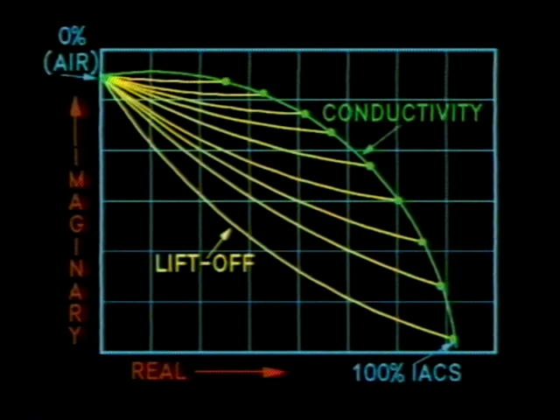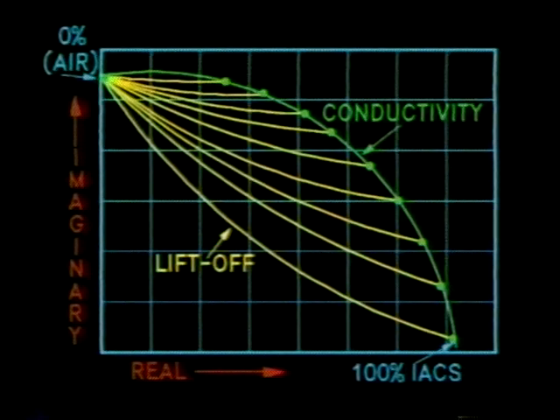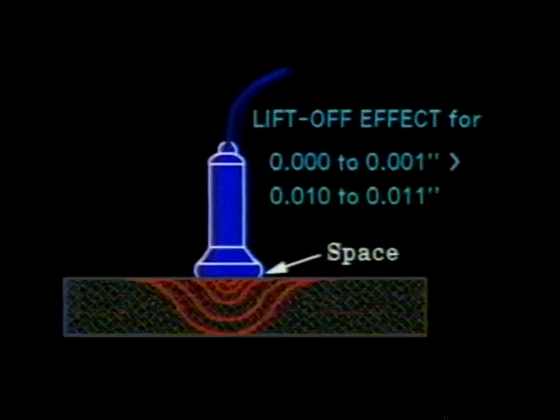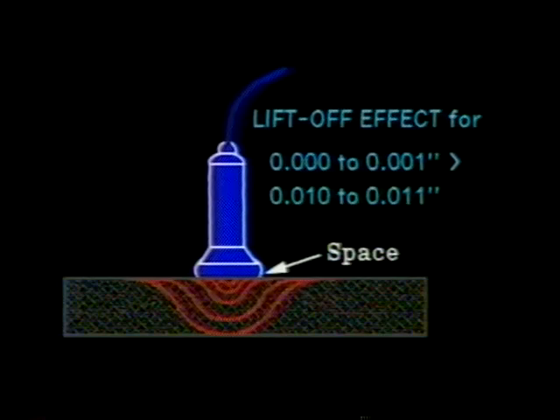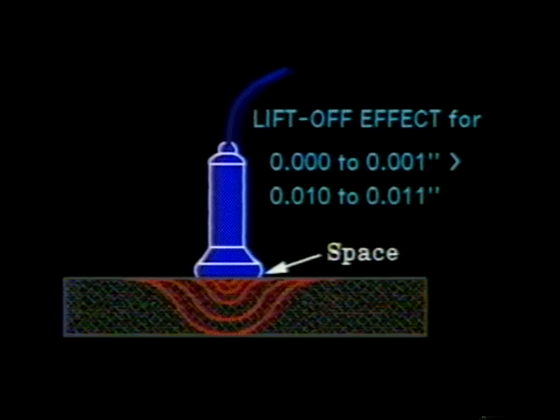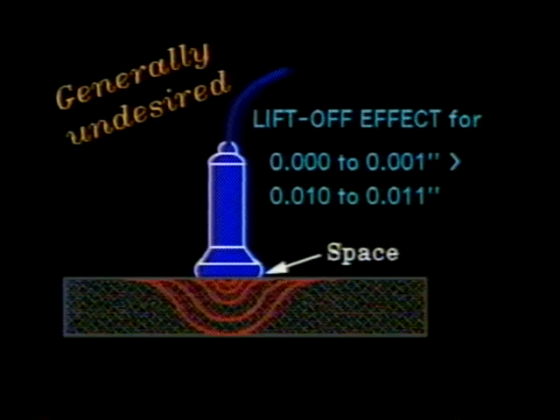The chart shows the relationship between air, conductive materials, and liftoff. The electromagnetic field is strongest near the coil and dissipates with distance from the coil. This fact causes a pronounced liftoff effect for small variations in coil-to-object spacing. For example, a spacing change from contact to 0.001 inches will produce a liftoff effect many times greater than a spacing change of 0.010 inches to 0.011 inches.